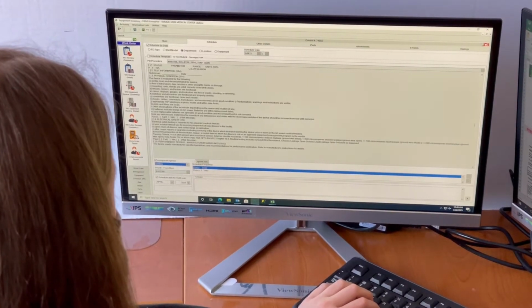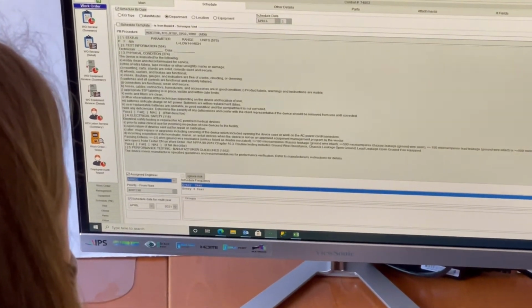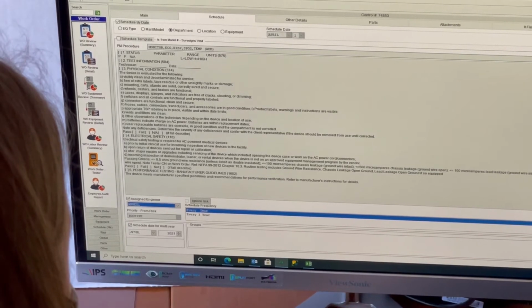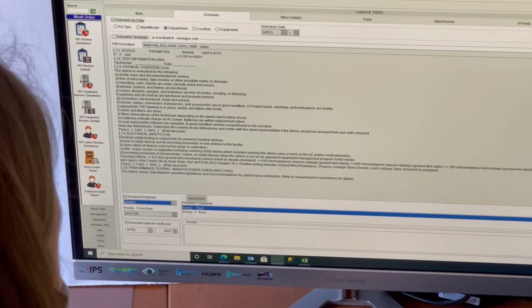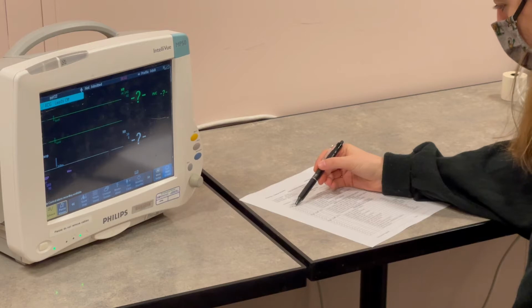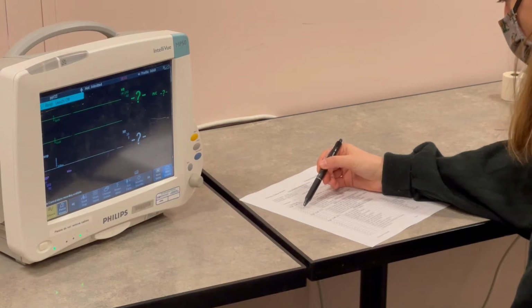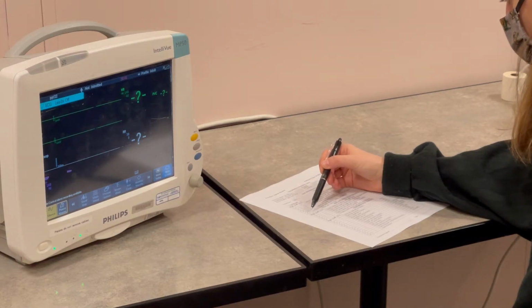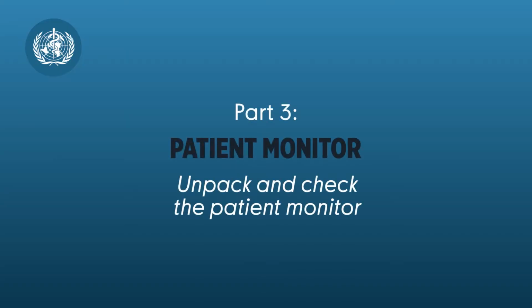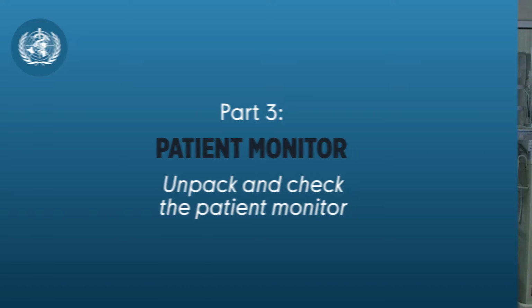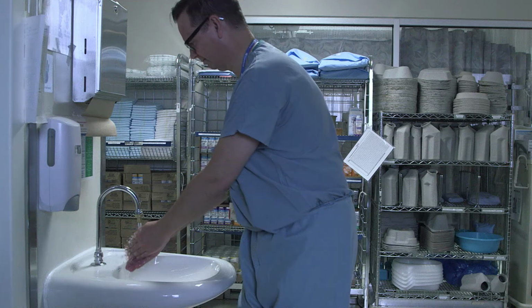Make sure you document the acceptance testing results in the database system you use at your healthcare facility to record device information, dates, schedules, and other data. If you don't use a database system, document the testing results on a checklist or paper record and file it with the patient monitor record. Now you are ready to unpack the patient monitor and any other boxes that came along with it. The boxes may have been opened already by someone at your facility who received the shipment just to verify the contents. Make sure your hands are clean by soaping and washing.